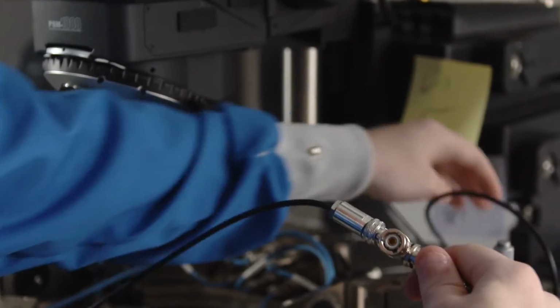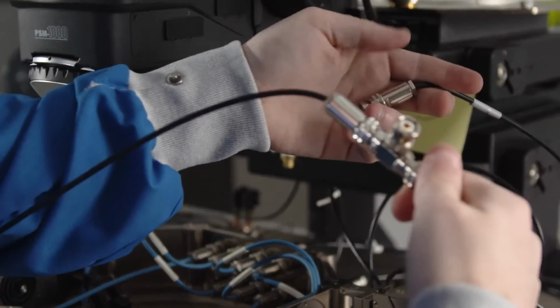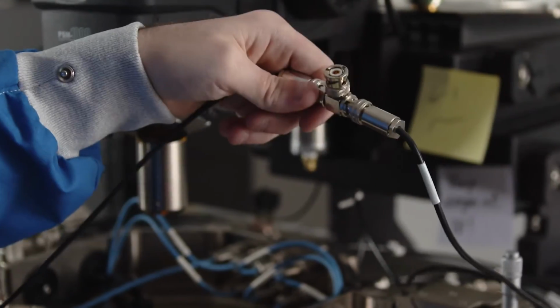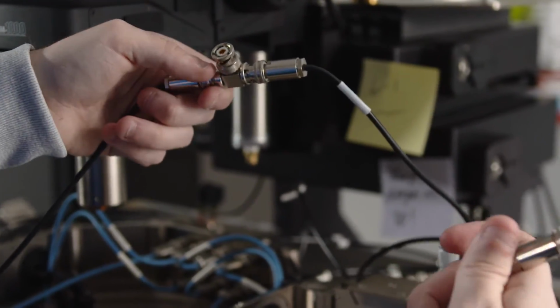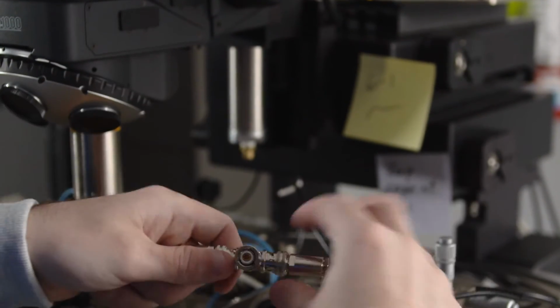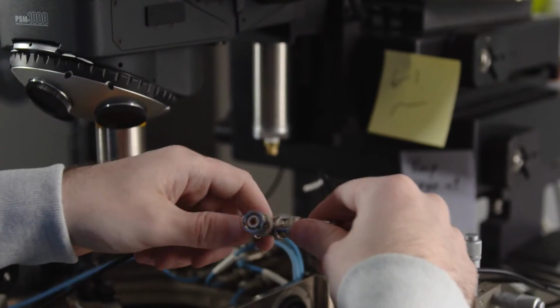We're here today in the Keithley Labs to show you a few tips and techniques on how you can make AC impedance measurements along with DC IV measurements. As some of you may have experienced, when making these different types of measurements, you have to end up changing your test setup, change your cables, even lift the probe needles off your device under test in order to make the change in the setup. This often is very time consuming and can lead to errors.